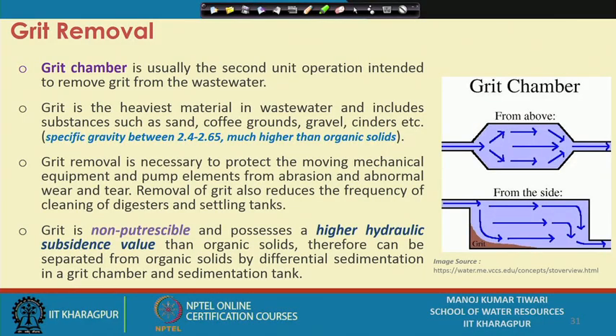Once the large floating materials have been retained, the next unit is the grit chamber. The grit chamber is usually the second unit operation, intended to remove grit from the wastewater. Grit is the heaviest material typically, and includes substances such as sand, coffee grounds, gravel, and cinders with significantly higher specific gravity. The typical specific gravity of grit materials is of the order of 2.6, with a range between 2.4 to 2.65, which is much higher than that of typical organic solids.